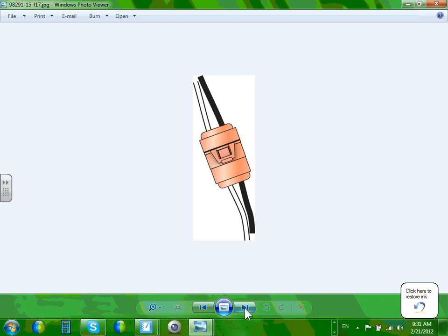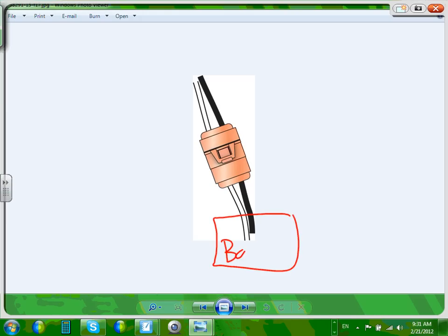Okay, let me see. Yeah, in 2008, Dustin, they said, if you have a double-ended fluorescent light, like this one above your head, two ends, you have to have a disconnect for the ballast. In 2011, they said, even if you change the ballast on this one, you have to have a disconnect. The industry guys have standardized with this tiny little disconnect. So this will be going to the ballast, from here and here at 1 amp, right?